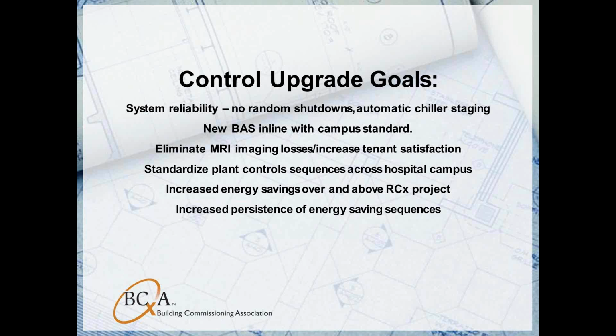By doing an upgrade, our BAS would be in line with the campus standard. By improving the chilled water plant operation, we eliminate MRI imaging losses and increase tenant satisfaction. We also made an attempt to standardize plant control sequences across the hospital campus. This hospital has several chilled water plants on their campus, and where possible, we tried to standardize the sequences. A good example of this is the de-icing mode on the cooling towers. We basically just pulled that identical sequence from an existing chiller plant and plugged it into this plant. That helps the facilities staff with operations because they know what to expect across their campus, and it's a big benefit for them.